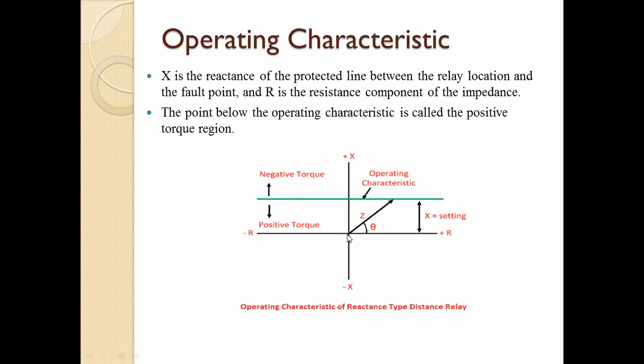Now here you can see on this RX diagram it is shown that up to your green line, this is your set reactance. Okay, means just like our impedance relay, we are setting here the reactance value. So within that, if the reactance value is less than the set value, then your relay is operating, and if it is above, then your relay will not operate here. Okay, so just like your impedance relay, the same characteristic is there.